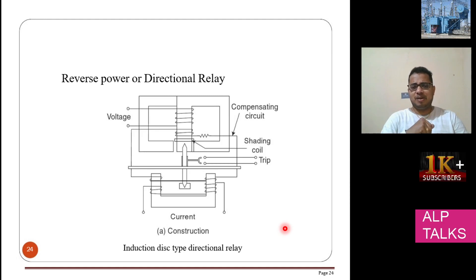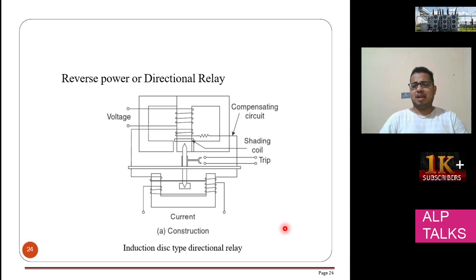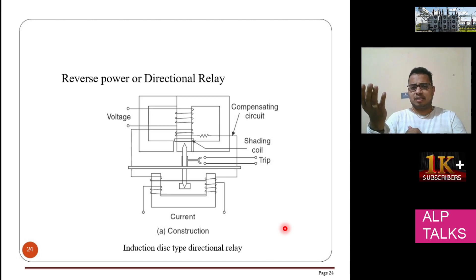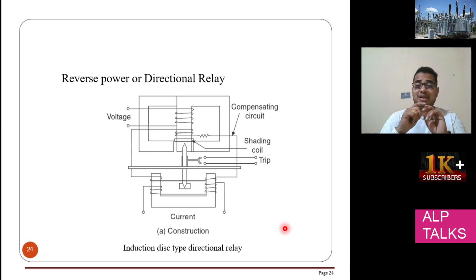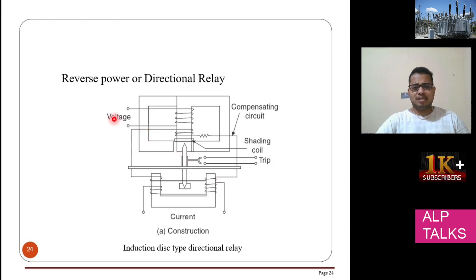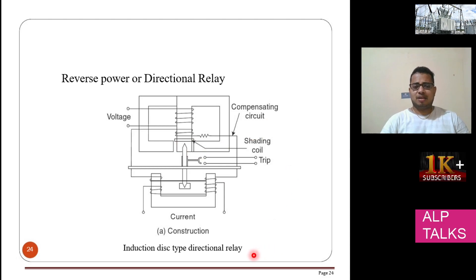There are some mechanical relays used when current can flow from one direction or the other, or when power flows in reverse direction. This generally happens when, for example, a generator gives supply to the grid, and when the generator has some issue, it takes power from the grid — causing reverse power flow. In that case, a reverse power or directional relay should be used to block the reverse flow. For a directional relay, voltage and current are combined. A shading coil and compensating circuit are used, along with a trip command output.